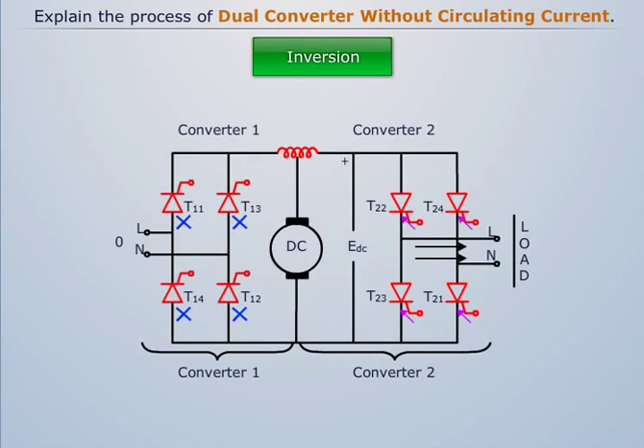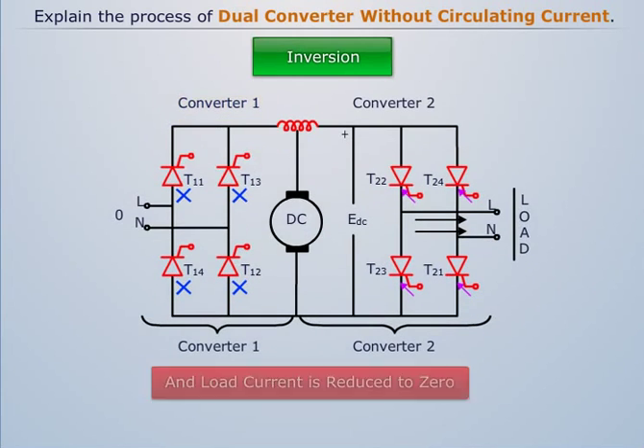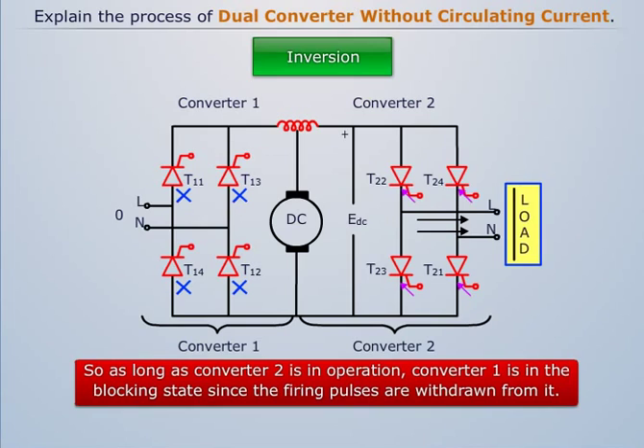For the inversion operation, converter 1 is first blocked by removing its firing pulses and load current is reduced to zero. And converter 2 is made to conduct by applying the firing pulses to it. The current in converter 2 would now build up through the load in the reverse direction. So as long as converter 2 is in operation, converter 1 is in the blocking state since the firing pulses are withdrawn from it.